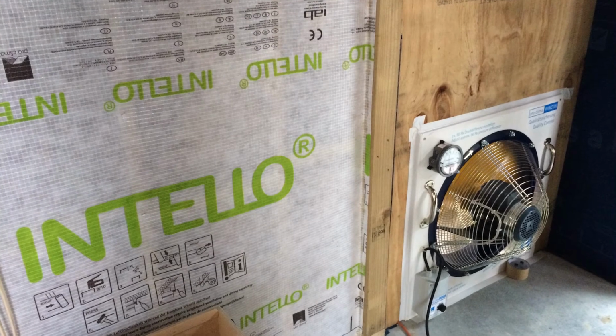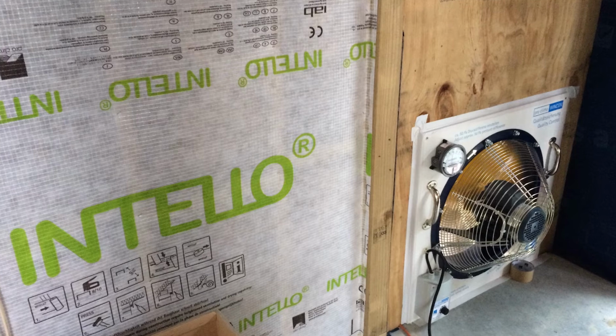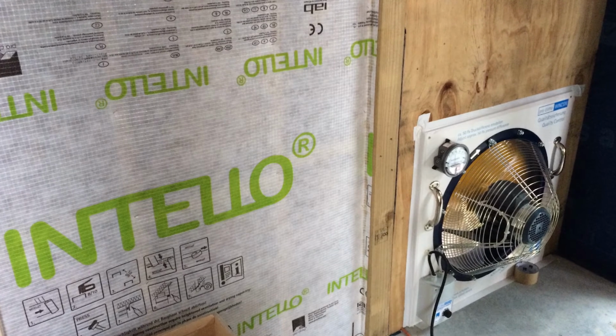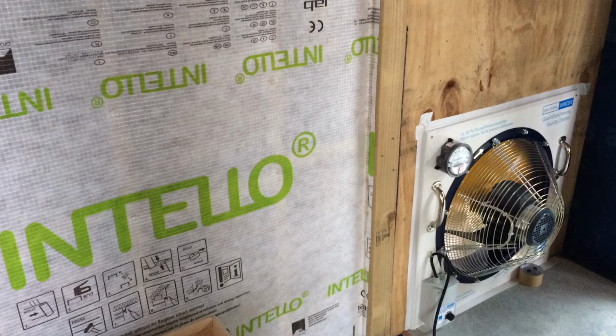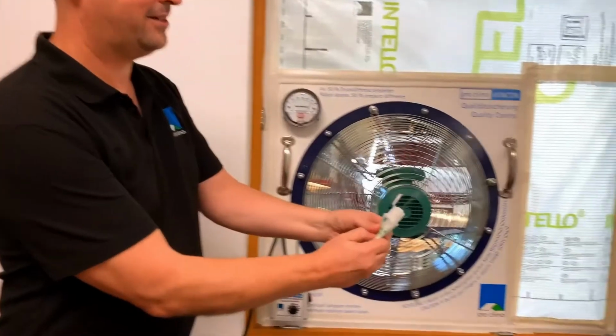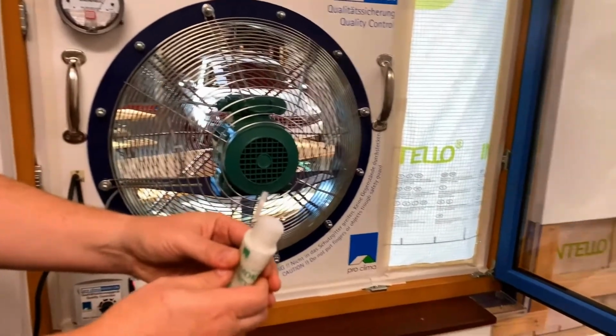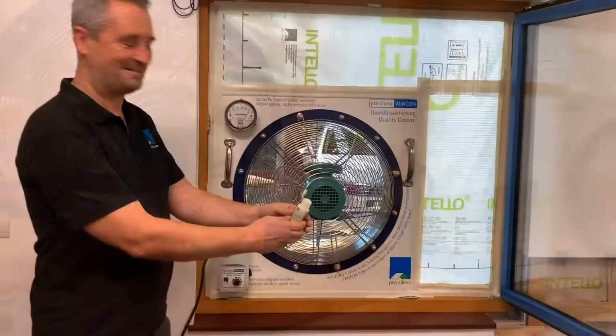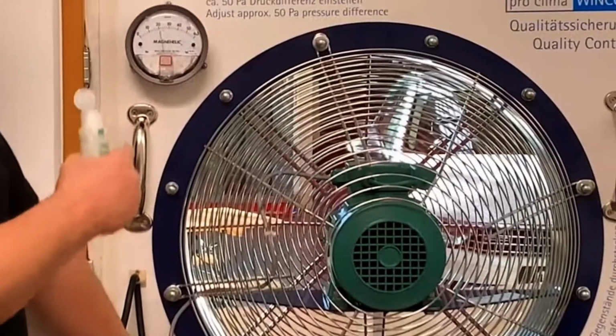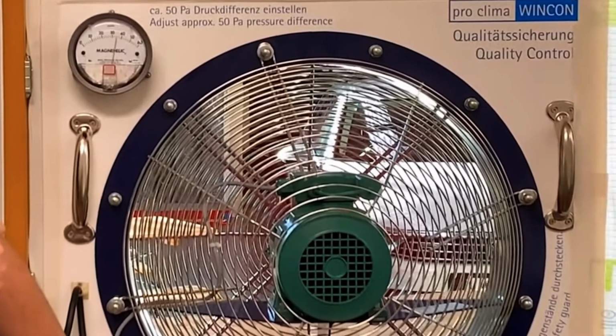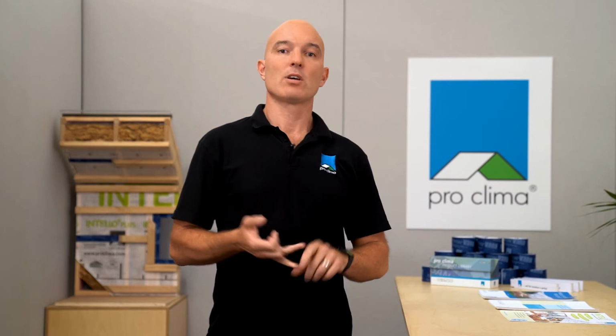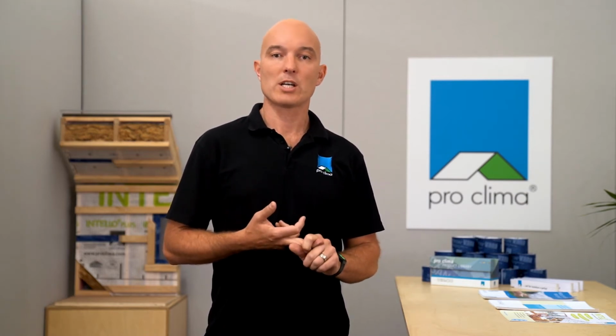When specifying or installing the pro clima INTELLO airtightness system, you have free access to the pro clima WinCon quality control tool. WinCon is essentially a manual fan unit which is fitted into an external window or door opening and depressurizes the building envelope. This allows you to identify unwanted air leakage through the airtightness layer, which commonly occurs via unsealed connections, overlaps, or where you have penetrations such as tricky junctions and the joinery.